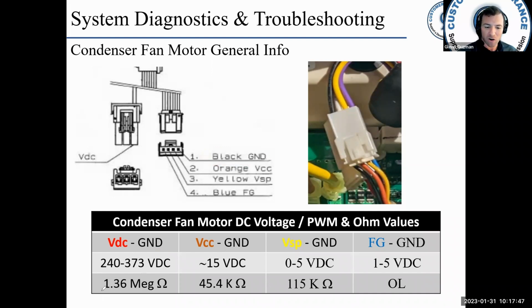If I'm ohming it out, it should be 1.36 meg ohms. So that's 1,360,000 ohms. VCC is the orange wire. When checking it to ground, it should be around 15 volts DC. And if you're going to ohm it out, 45.4 K ohms, so 45,400 ohms. VSP to ground should be 0 to 5 volts DC and around 115 K ohms. FG is a signal wire, a feedback wire. It should be around 1 to 5 volts DC. And if you're ohming it to ground, you're going to get OL. These are normal approximate readings.